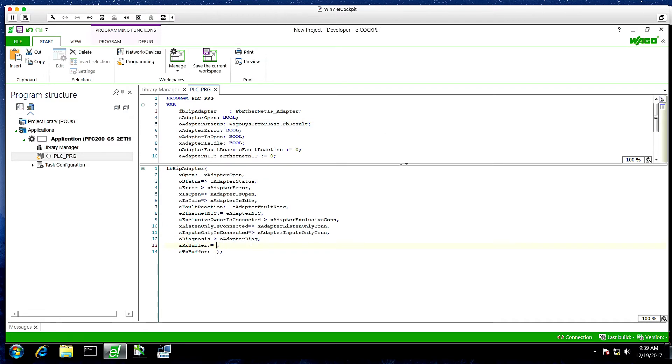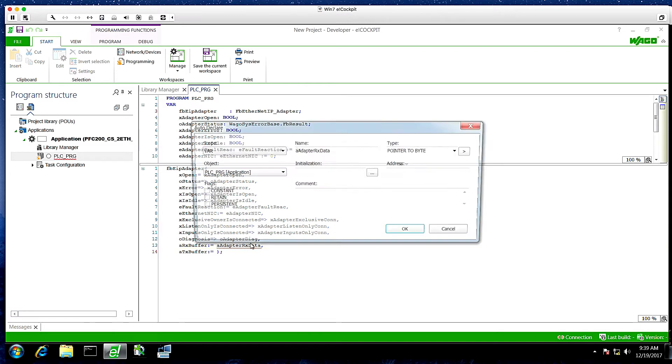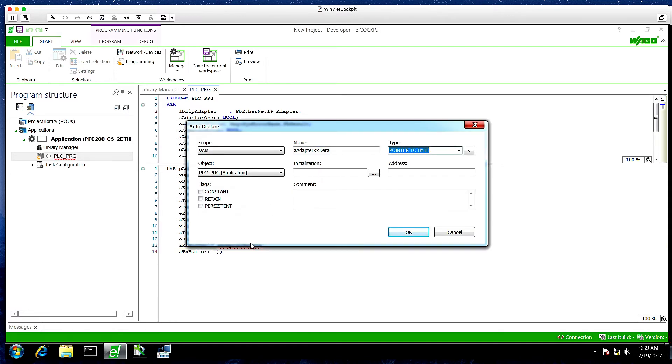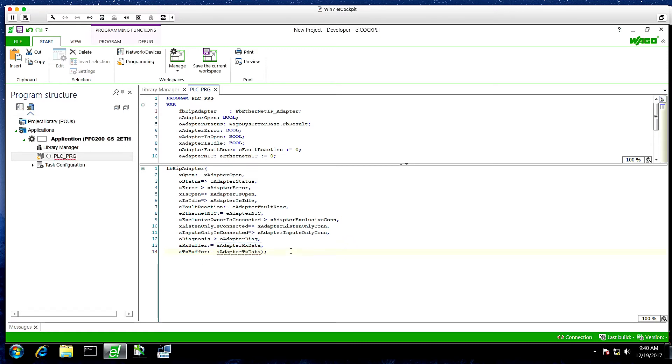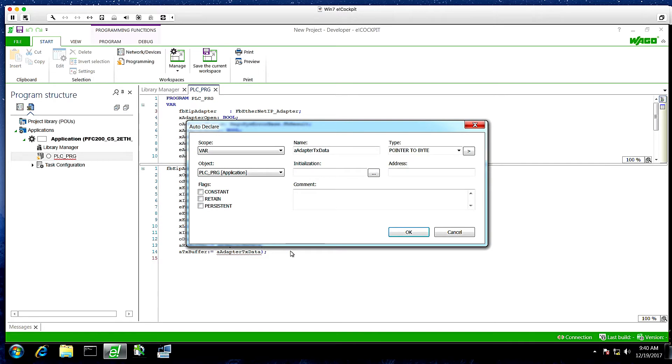So the function block will automatically resize the EIP adapter for the size of the data array. So we're just going to do 10 bytes in and 10 bytes out. So we're going to change this to an array of 0 to 9 bytes. And we'll do the same thing on the output. We'll make this an array of 0 to 9 bytes as well.